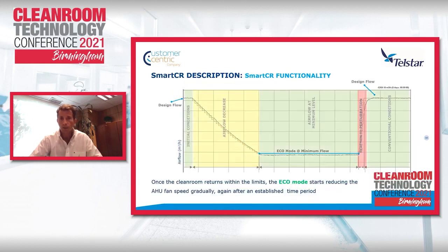Well, this is the same slide explaining the three stages, coming from a conventional setup, the decrease of airflow to reach the minimum flow of the installation. Again, we are not talking about a single room, but several rooms, several air handling units, and everything affecting one another. We have the reaction time, and then a period of working under conventional conditions.